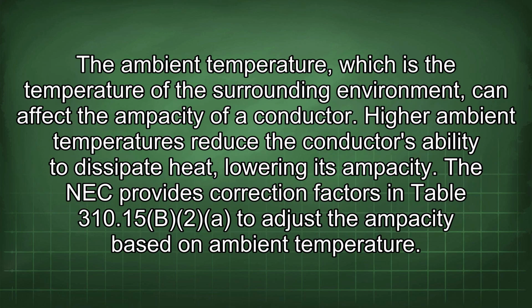The ambient temperature, which is the temperature of the surrounding environment, can affect the ampacity of a conductor. Higher ambient temperatures reduce the conductor's ability to dissipate heat, lowering its ampacity. The NEC provides correction factors in Table 310.15(B)(2) to adjust the ampacity based on ambient temperature.